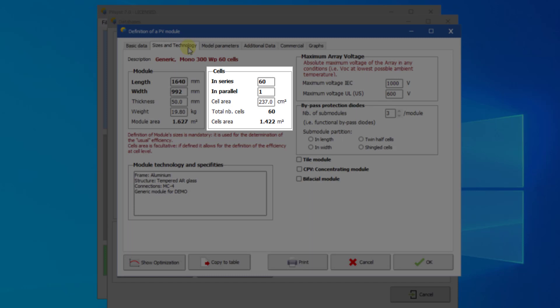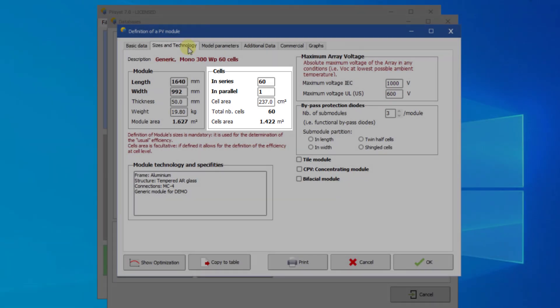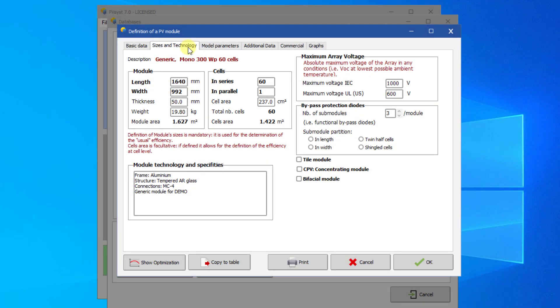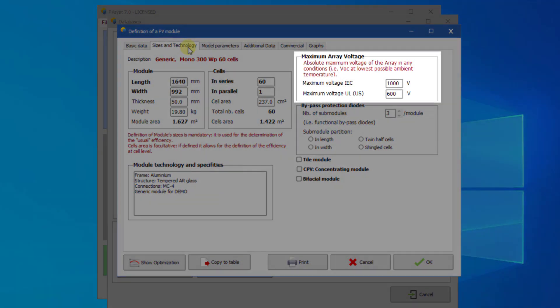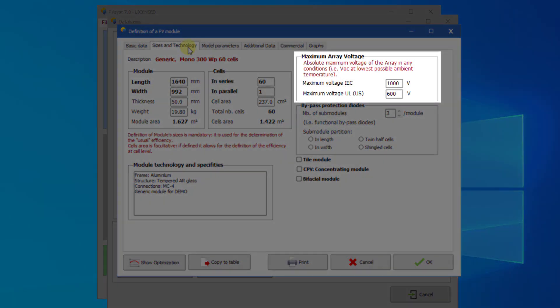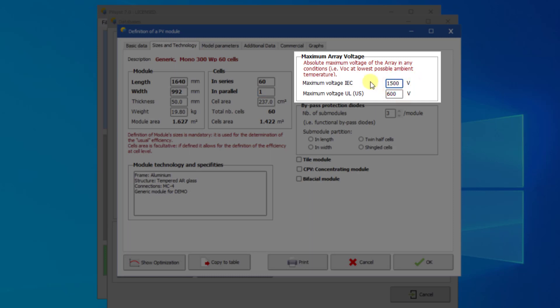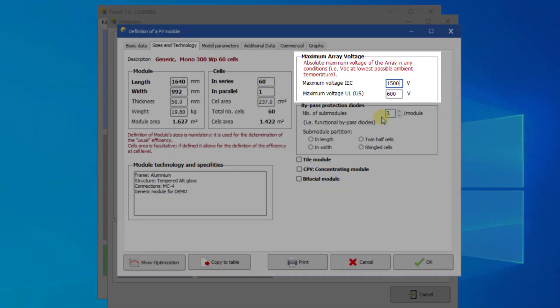The cell area is optional. If defined, it will allow to calculate the efficiency at the cell level. For the maximal array voltage, the IEC value is usually 1000V for standard PV modules. Nowadays, more and more modules are specified for 1500V to be used in high voltage PV systems. In the US, some modules are specified for 600V due to special regulation rules for electrical systems.